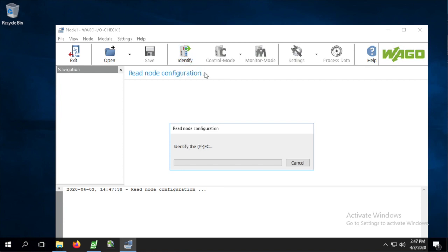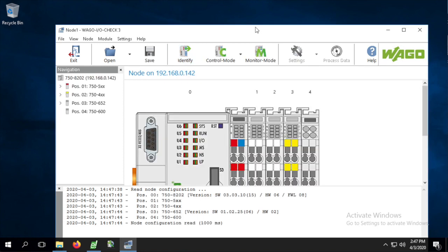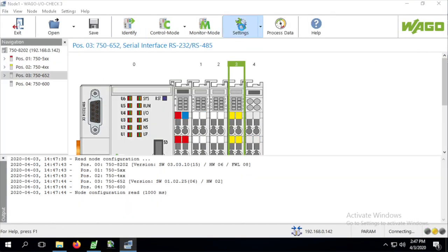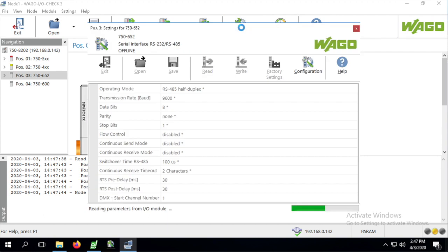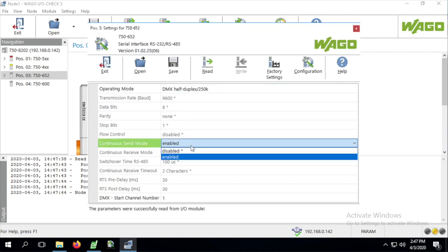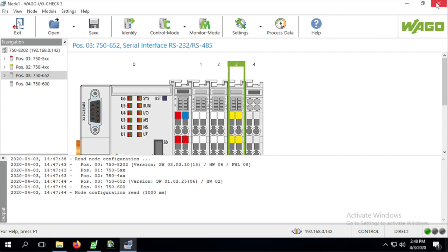The 750-652 module needs some configuration through I.O. check before it can be used as a DMX master. Open the module settings and make sure the operating mode is set to DMX half duplex 250k and that continuous mode is also enabled. Write any changes to the module and then exit I.O. check.